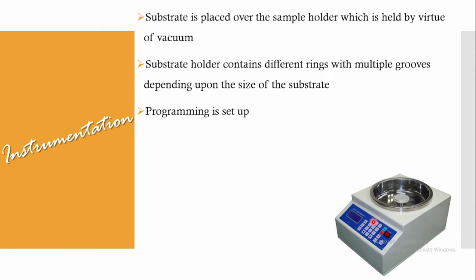So one thing we need to remember, generally the spin coaters are almost of similar functioning, but only some of the interface, that is the software interfaces, can be differing. The principle, the working, everything remains the same. And many a times in the setup one extra setting will be there, like ramp down step. So that setup ensures the spin coater doesn't stop abruptly.